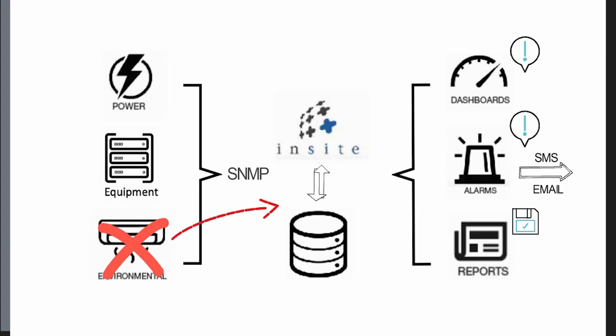So at this point, the apparatus room starts to heat up. But we've already got guys who are looking at it. These guys have been alerted. They have been informed. They can go in and try to get the aircon working, or at least try and make arrangements to take that transmission data, the audio, video, and whatever is feeding that transmission, away from this apparatus room so you can keep on air.